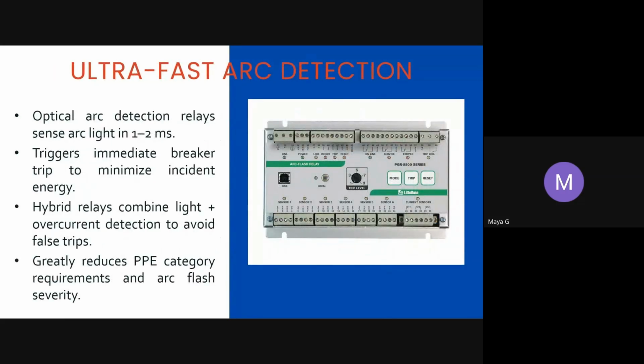Next is ultra-fast arc detection, or the optical arc detection relays. This particular relay senses arc light within 1 to 2 milliseconds and triggers an immediate breaker trip. Once a fault is recognized, the circuit has to be broken by using the breakers. So we need to give the trip signal to the breaker. Within 1 to 2 milliseconds, this relay senses and gives a trip signal to the breaker to minimize the incident energy. Hybrid relays combine both light and overcurrent detection to avoid false trips. This greatly reduces the PPE category requirement and arc flash severity.